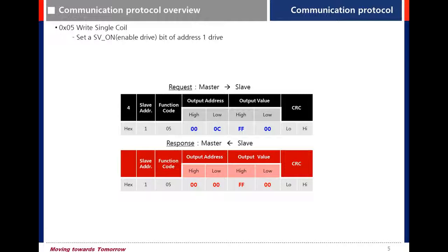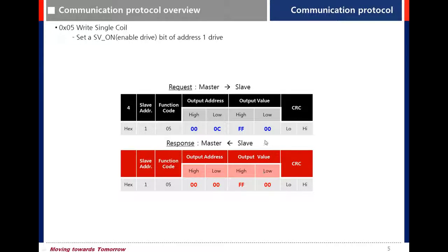Let's see the Write Single Coil command. For example, set servo on by writing: slave address is the node ID, function code 05, output address 0C — this is the servo on address, refer to the manual for addresses. Output value FF00 means bit on; 0000 means bit off.